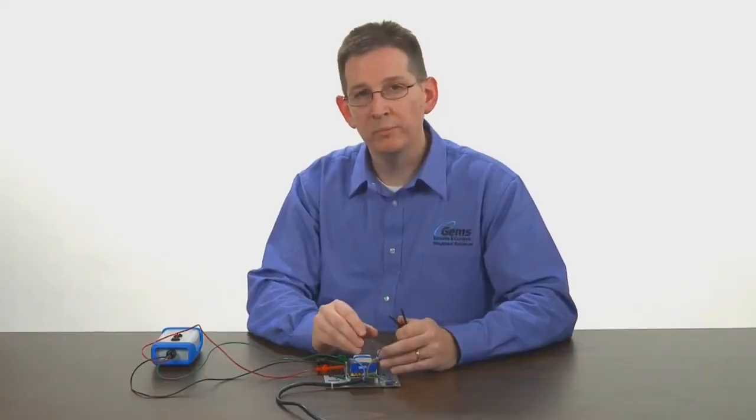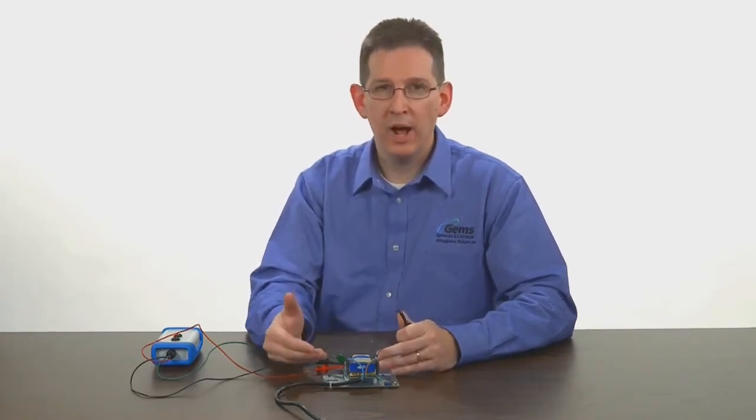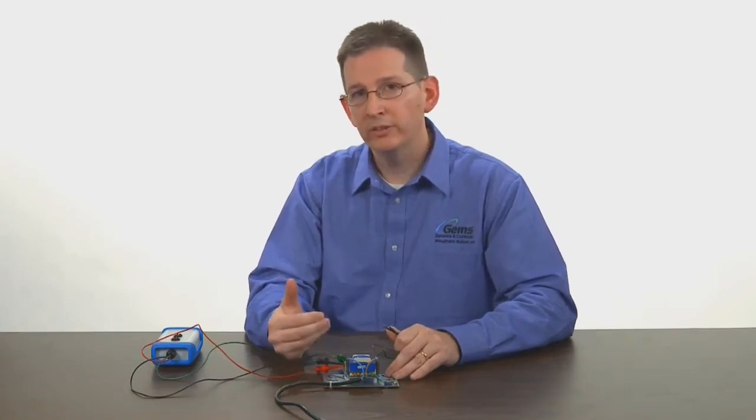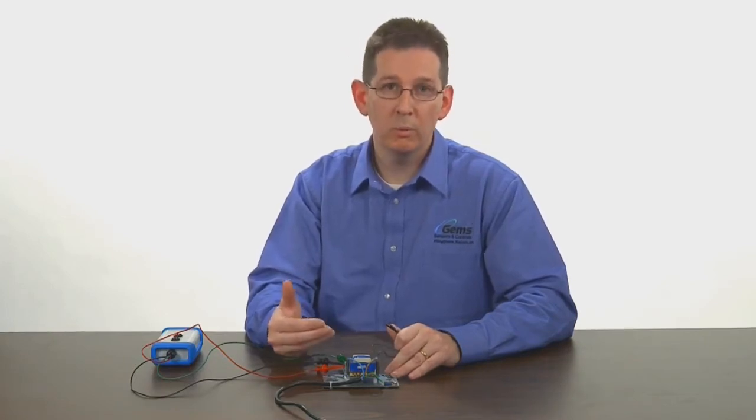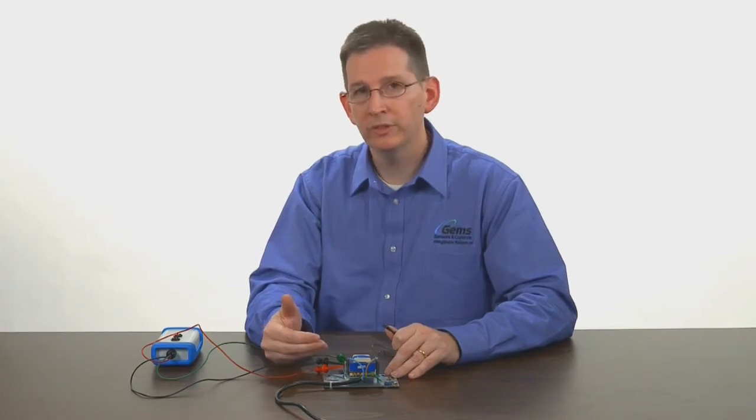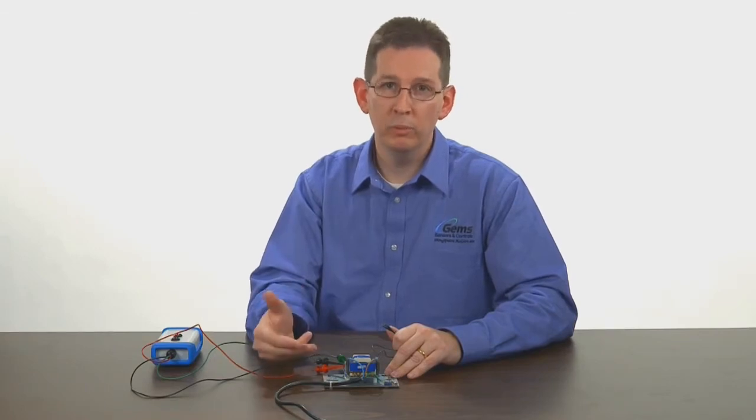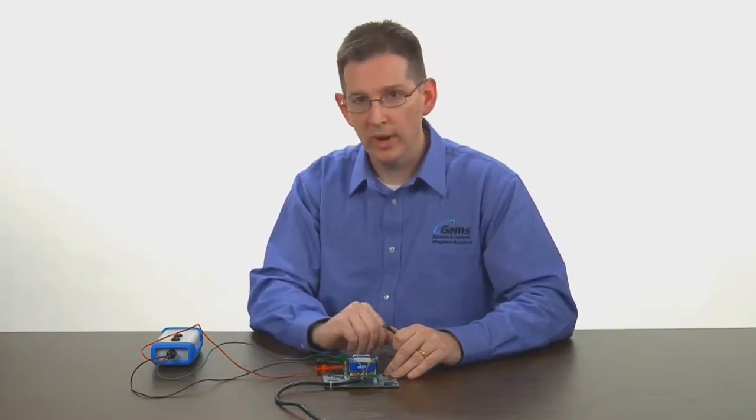This again is a direct mode unit. Should you have an inverse unit, the actions are opposite, meaning that the relay is energized when both probes are dry and de-energized when both probes are wet. In the differential case, for single level service, inverse mode, the relay is energized when the single probe is dry and de-energized when the single probe is wet.